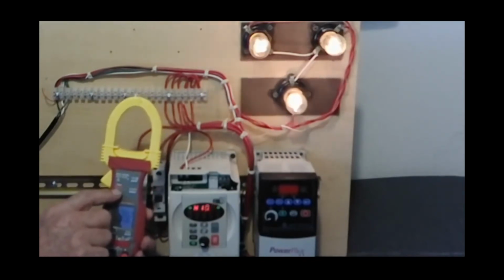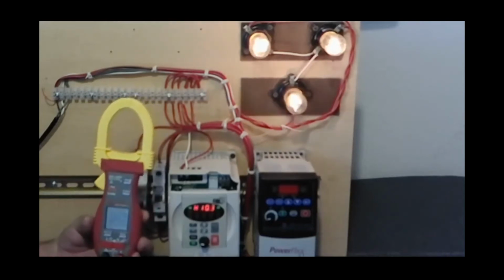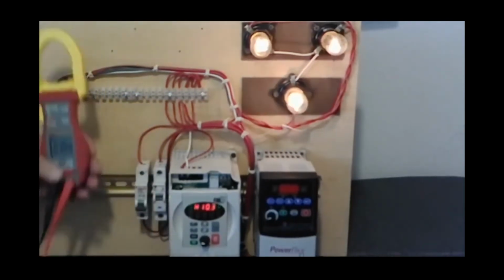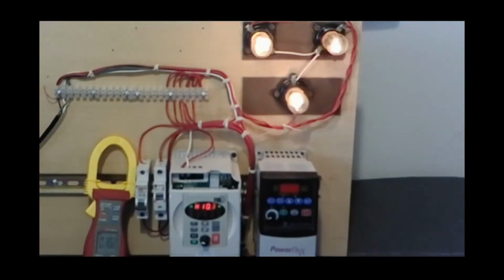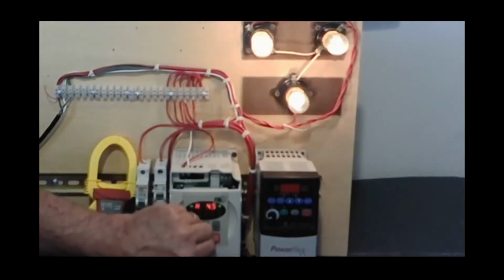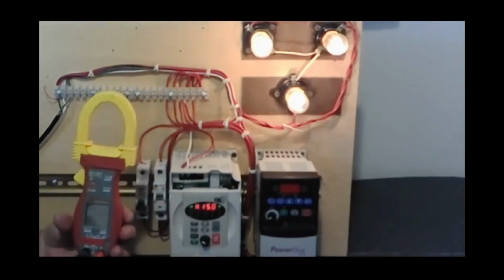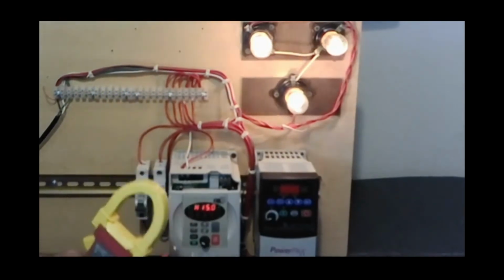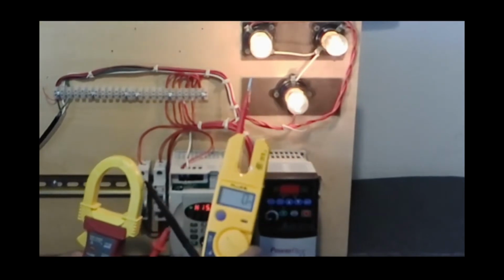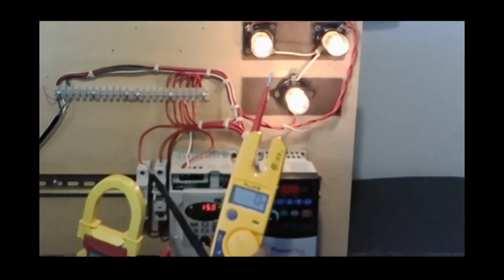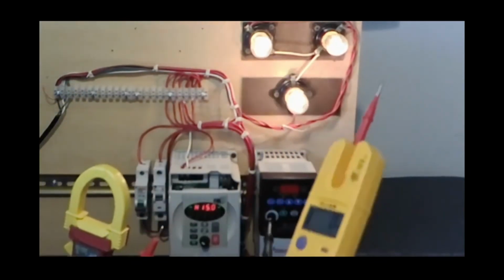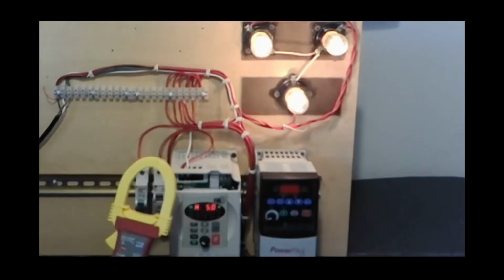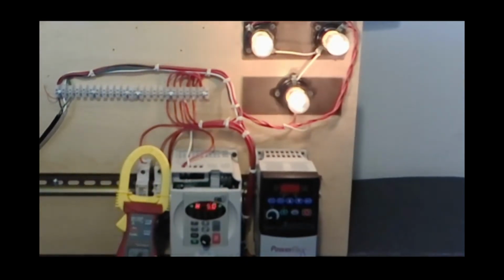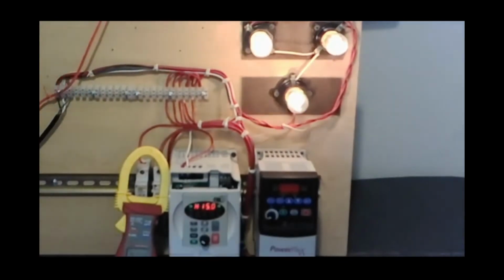So if we troubleshoot that drive, we've got to be using the right types of meters, otherwise you're shooting from your hips. Now if I increase this to 60 hertz, this meter says it's exactly 240 volts. If I increase to 60 hertz, this meter tells me it's 343 volts. Which meter's right? Obviously the true RMS. So there are different meters, and we have to have the different types. Now one easy method is I can take readings right here on the bottom, which I cannot get a good view of with the camera. So I'm going to take readings right here on the load itself.